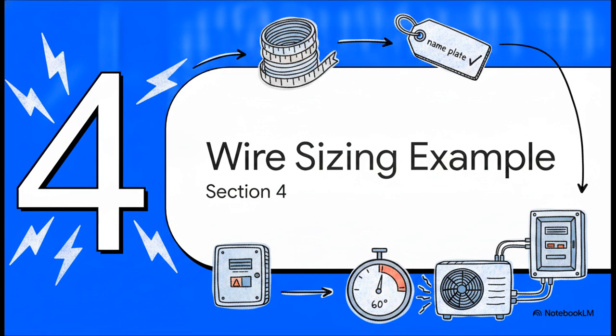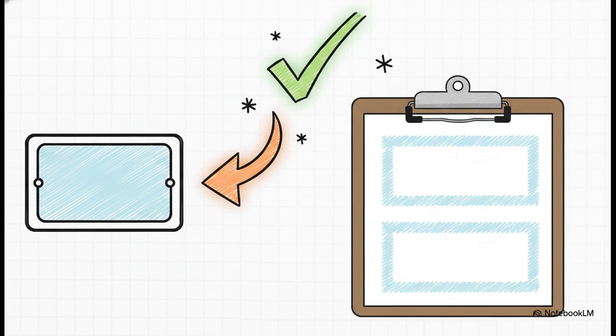All right, let's bring it all home in part 4, a real-world wire sizing example. Let's put all these clues together and solve an actual sizing problem, exactly like one you'd see out in the field. We know we're using Article 440, we know to check the nameplate, and we know to use the 60-degree column. So here's the data straight off our theoretical AC unit. The minimum circuit ampacity, the MCA, is 17.8 amps, and the maximum circuit breaker size is 30 amps. Remember, the manufacturer already crunched that 125% math to give us that 17.8 amp figure. That is our absolute baseline.